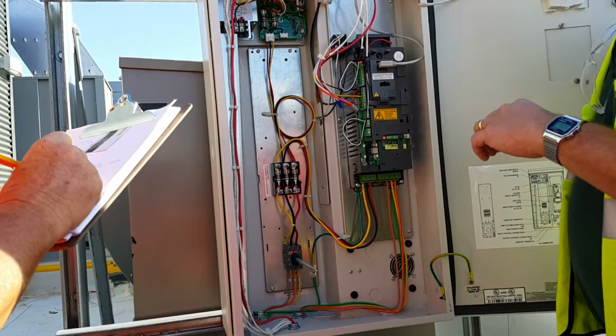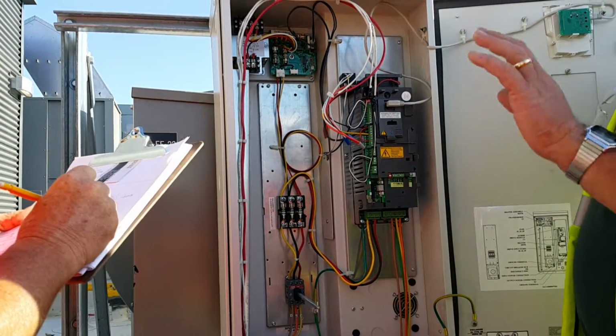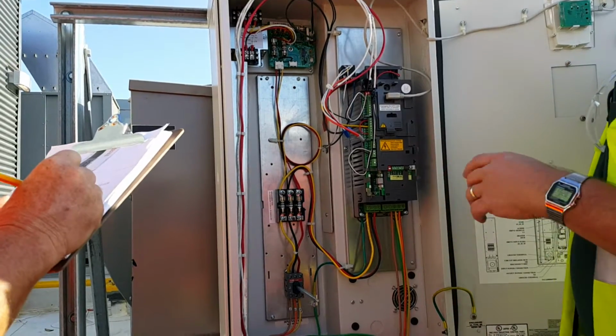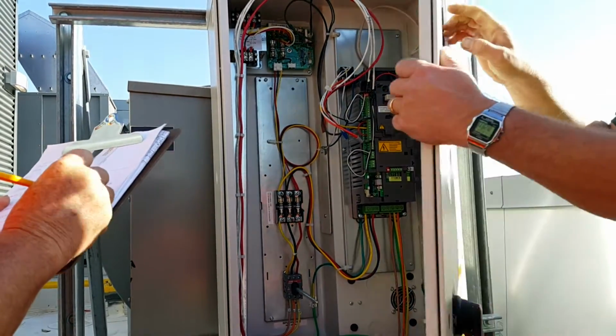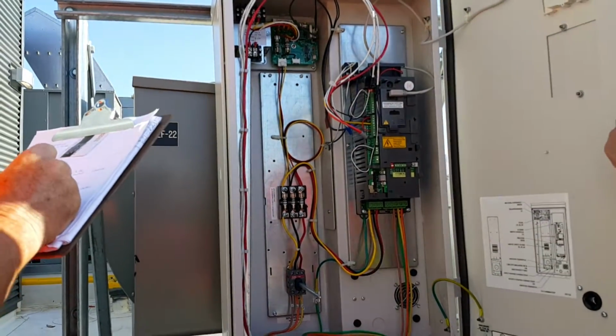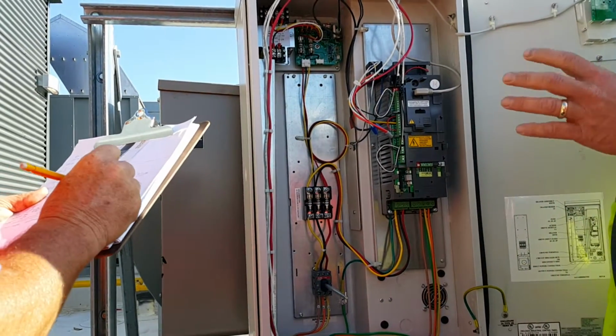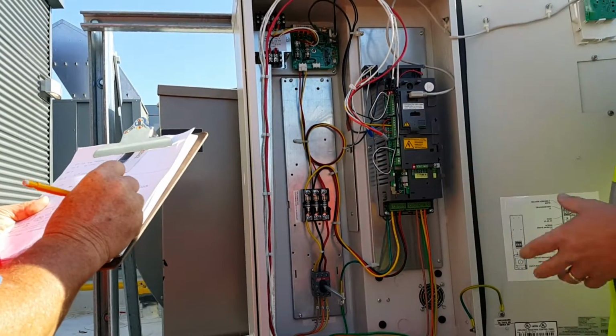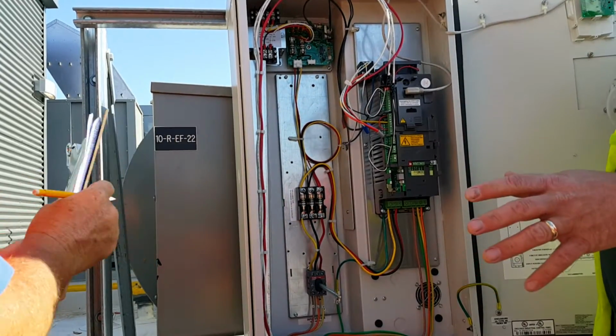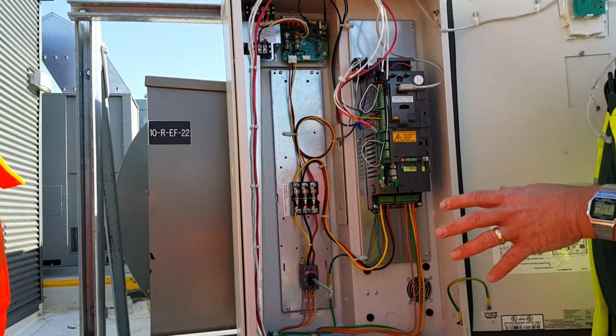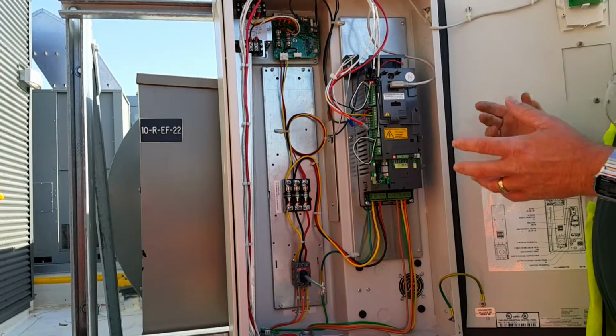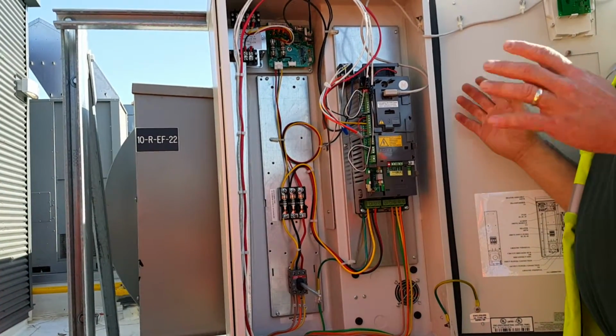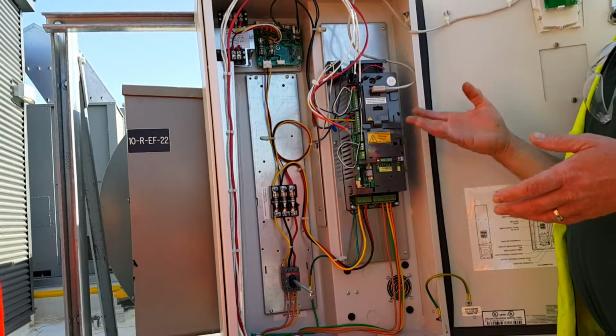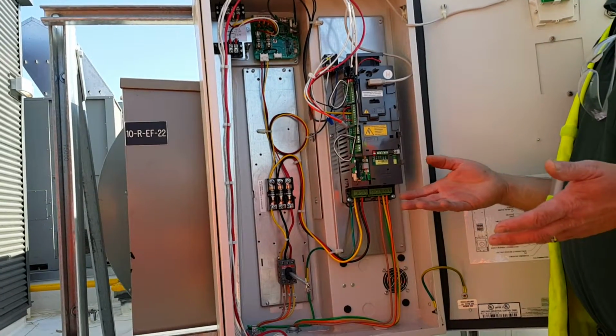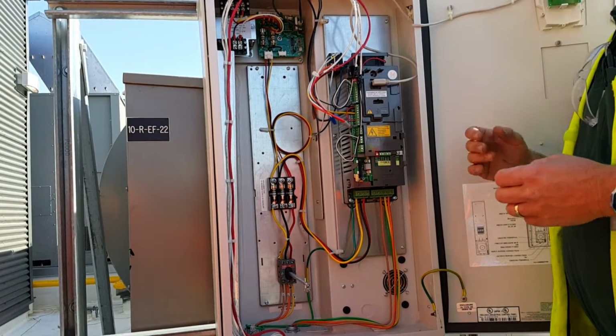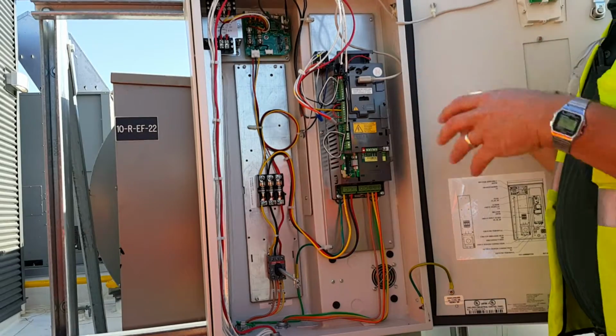Next step to do is put it in hand. If you run it in hand, that means the drive's okay. So if you put it in hand up here on the keypad and run it up and down, the drive itself is fine. What happens is a lot of people get tunnel vision around a drive because it's a fancy piece of equipment, and they lose their normal troubleshooting things, and they get focused on the drive. Meanwhile, the drive is sitting there. If it doesn't have a fault on it and it's just sitting there, chances are the control system is, for whatever reason, not telling it to run. But they always kind of focus on the drive.